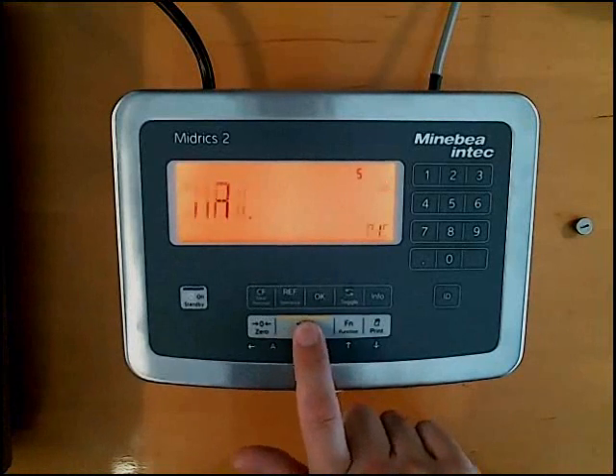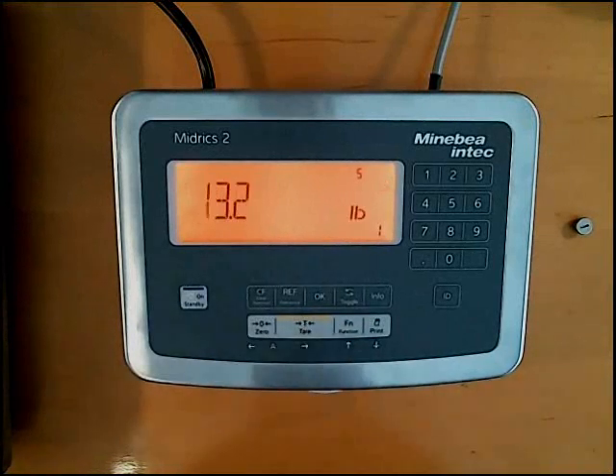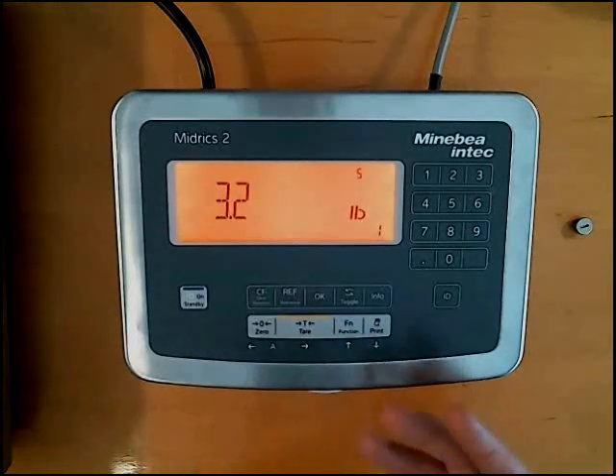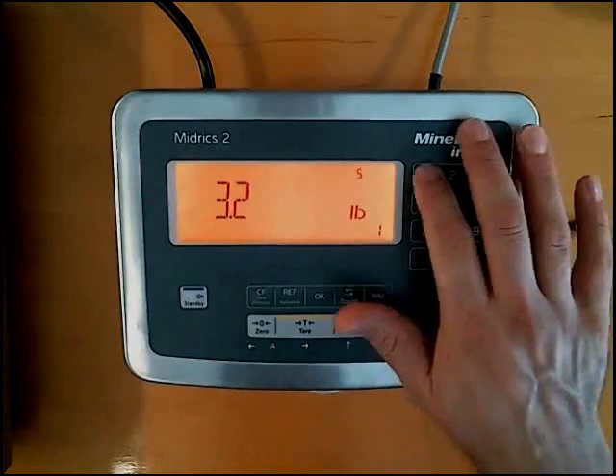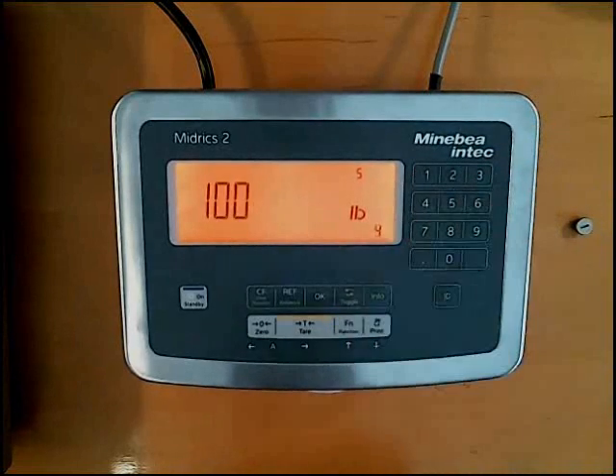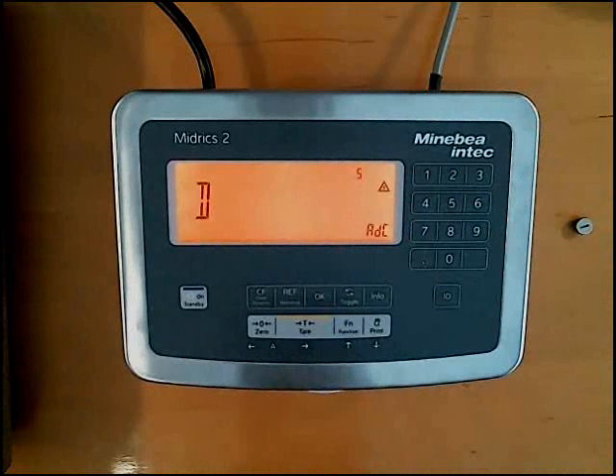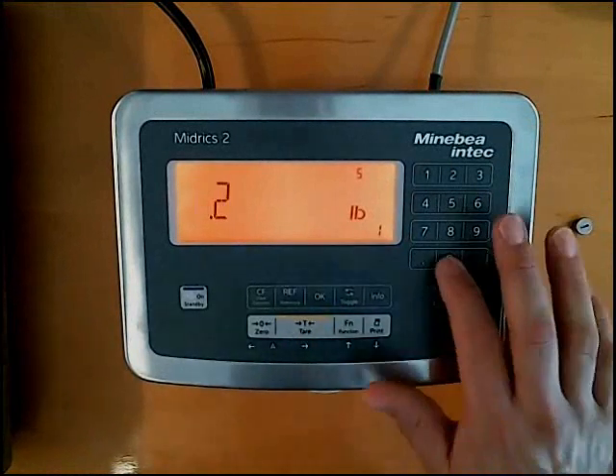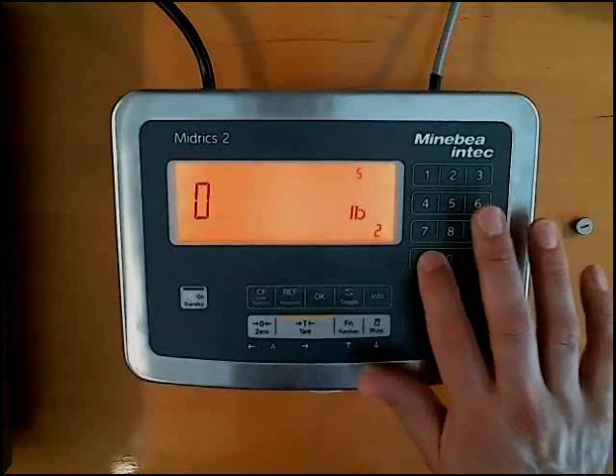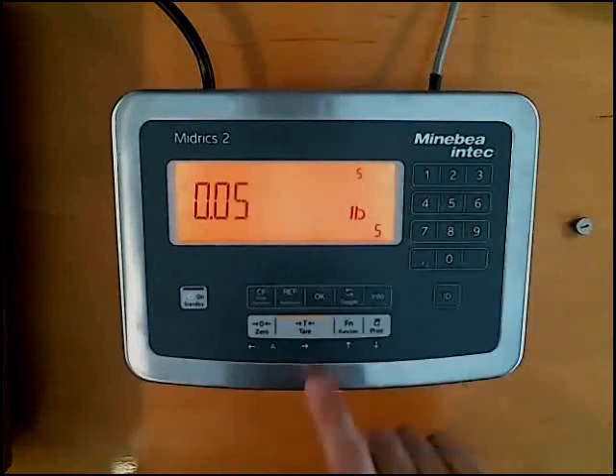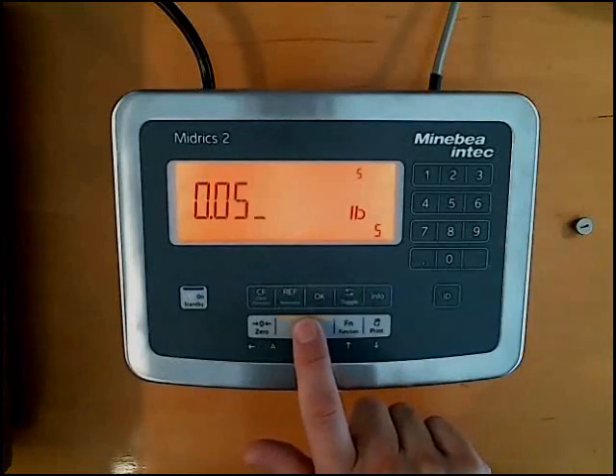At this point, you'll press the tare key and you'll set in your span or your maximum capacity. You can go right to the keypad. I'm going to type in 100 pounds, press tare. Then you'll see D. D is your digit or grad size. So go ahead and push tare again. This one is set up to 0.2 pounds. I'm going to go ahead and change it to 0.05. And as you can see, I was able to type right over the numbers that were shown in the display.